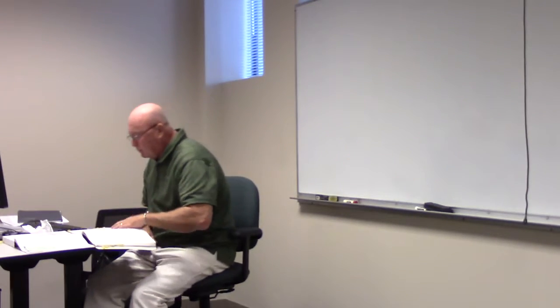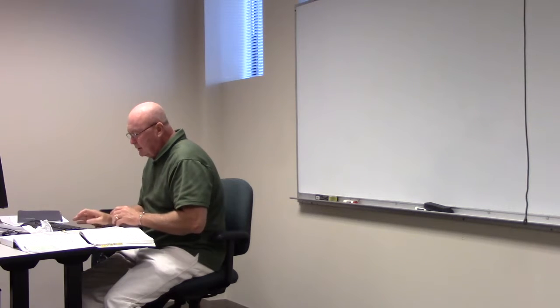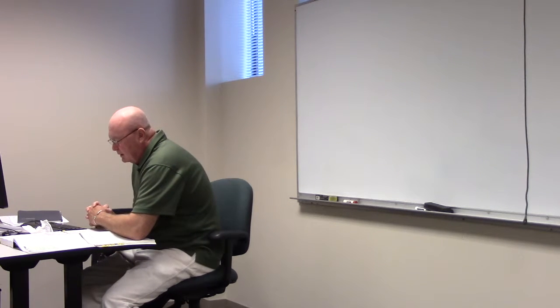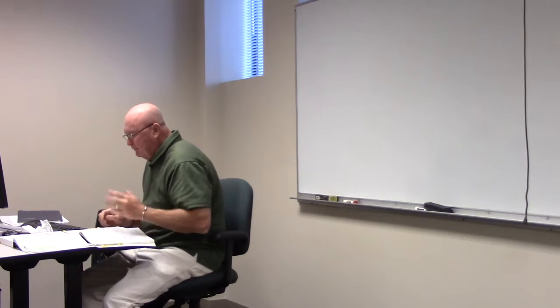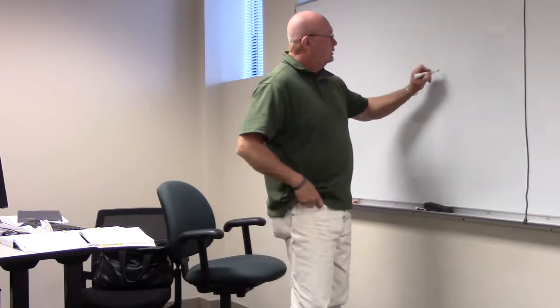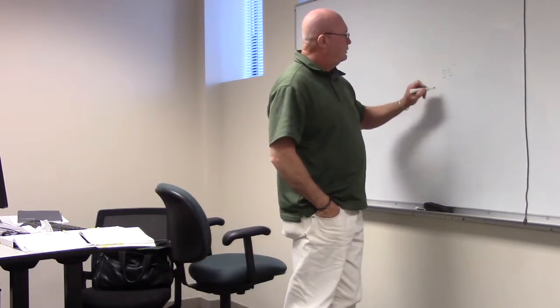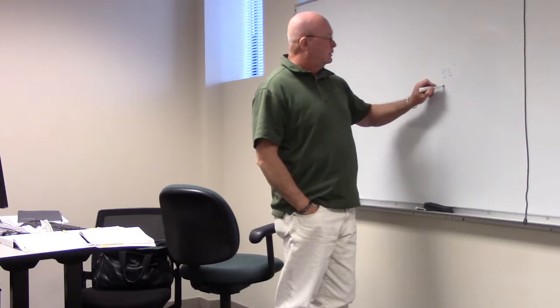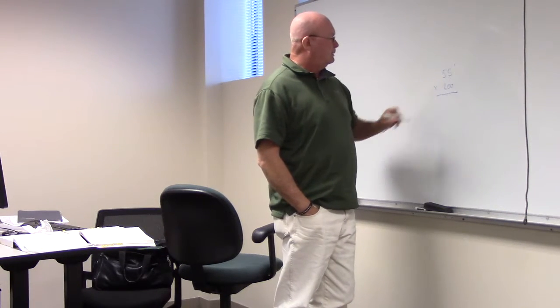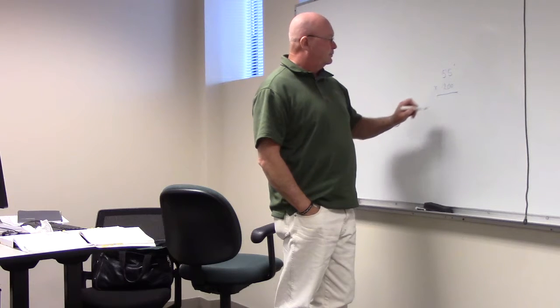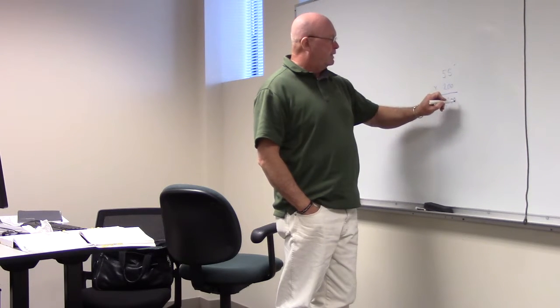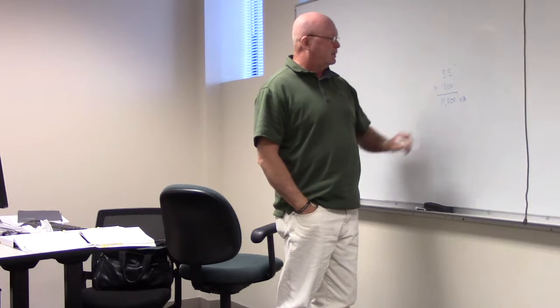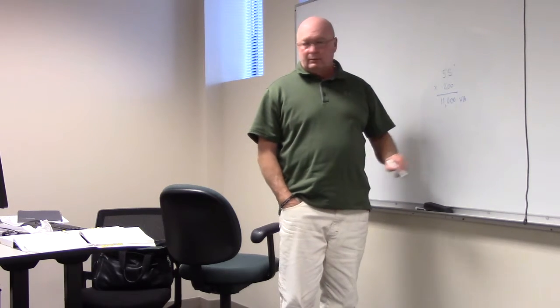All right, show window lighting, 220.14, we got an example here. It says show window lighting load is calculated at 200 VA per foot. So we got a 55-foot show window. What are we gonna do? Times it by 200. And we're gonna get how much? 11,000. Okay. Volt amps? Yes, sir. What does volt amps also stand for? Watts.